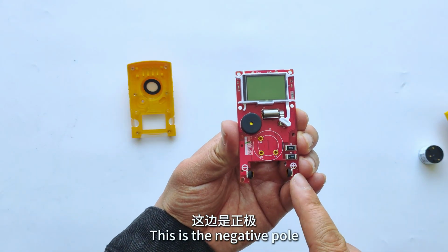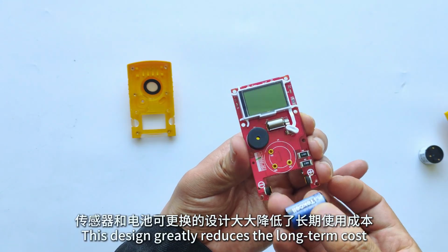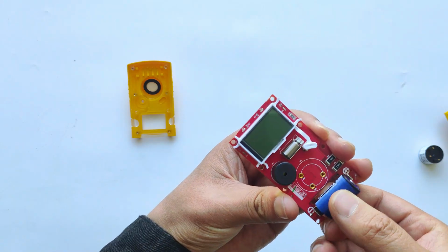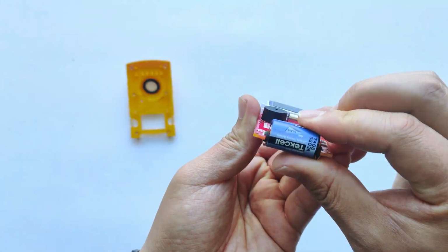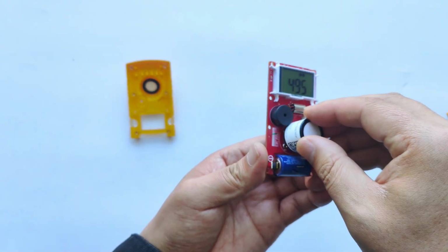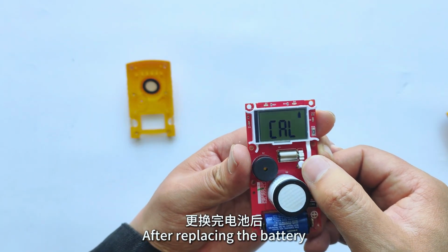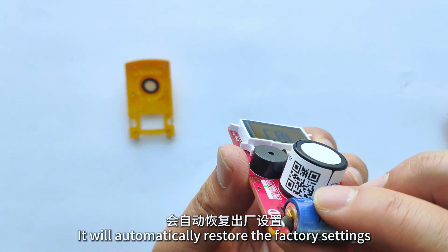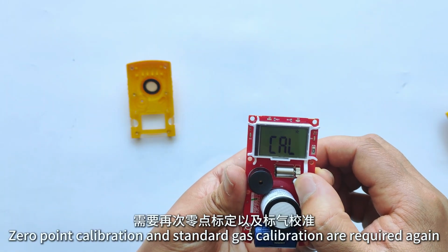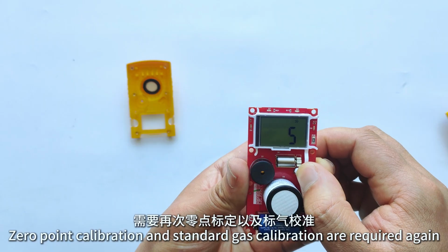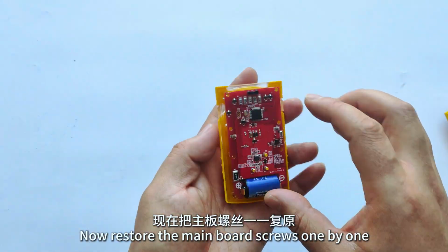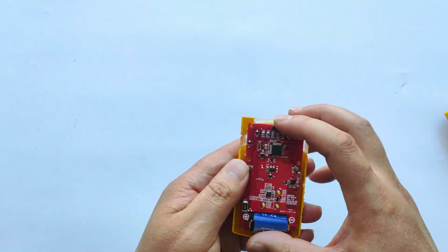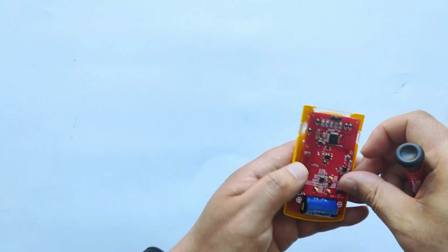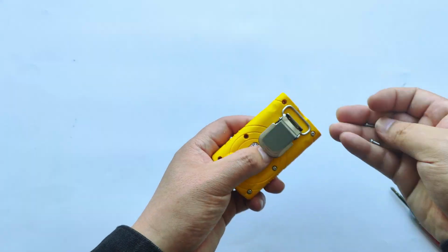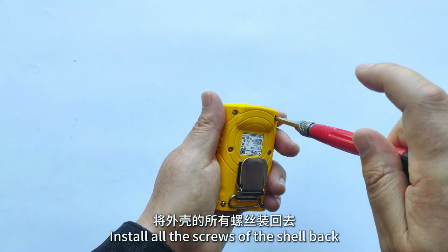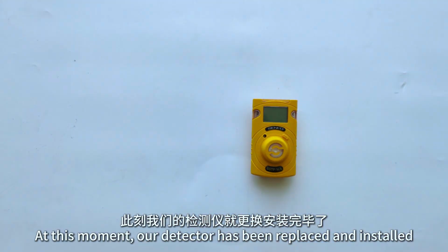This is the positive electrode. This is the negative pole. This design greatly reduces the long-term cost and is more environmentally friendly. Then install the sensor. After replacing the battery, it will automatically restore the factory settings. 0-point calibration and standard gas calibration are required again. Now, restore the main board screws one by one. Install all the screws of the shell back. At this moment, our detector has been replaced and installed.